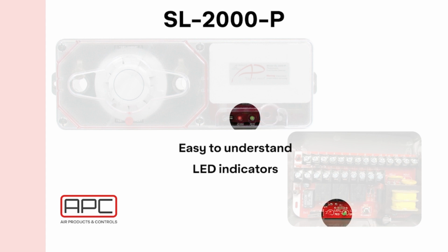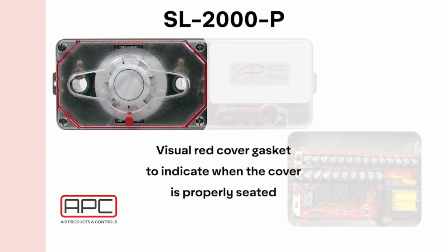The LED indicators on the board are easy to understand. Red equals alarm, green equals pilot, and off equals trouble. The cover switch provides instant feedback when the cover is removed. A red gasket around the sensor chamber becomes clearer as the cover is tightened. This gives an added visual indication when the cover is properly tightened.